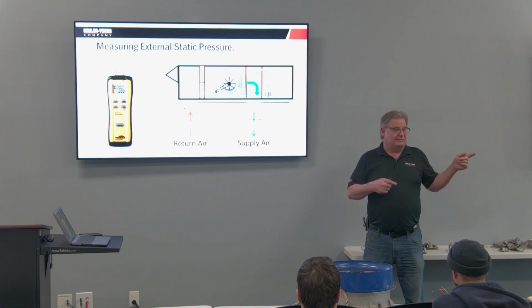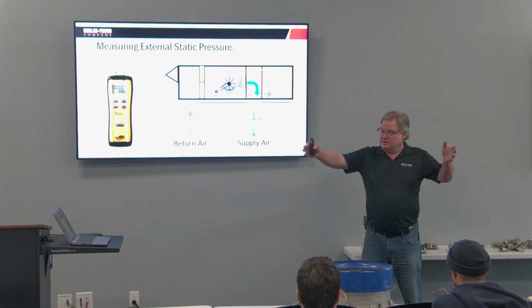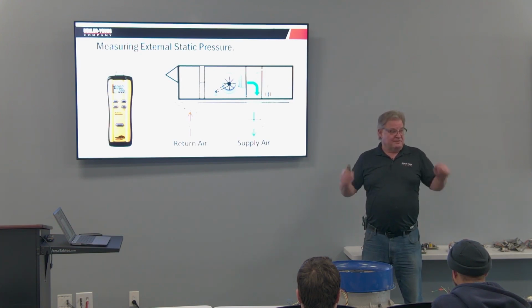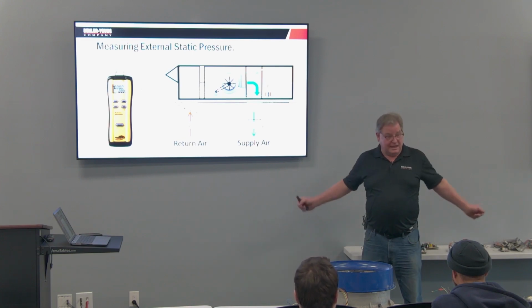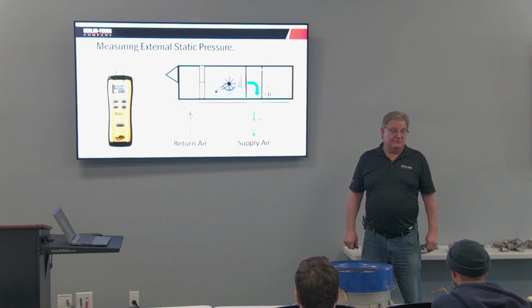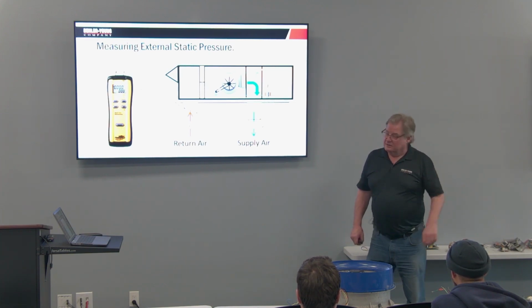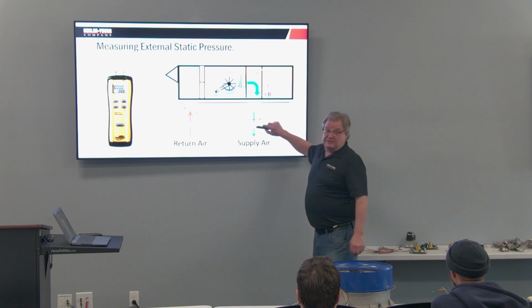So we go to BRYANT about 4 or 5 years ago. They have a rooftop unit sitting on a curb. They have the probes in the door, and then they had us put the probes in the ductwork. And it was about a 30% difference. So it's huge. So you cannot put the probes in the door to measure static. You got to go into the ductwork in the drops.